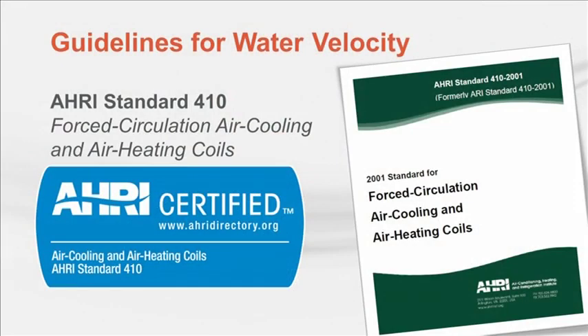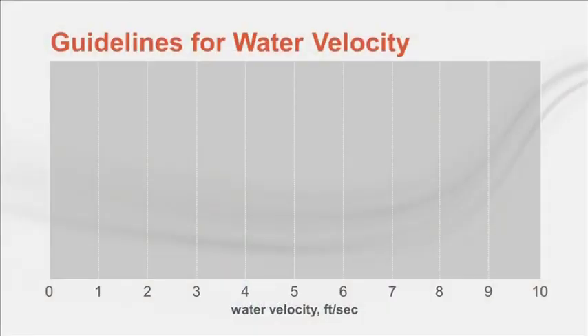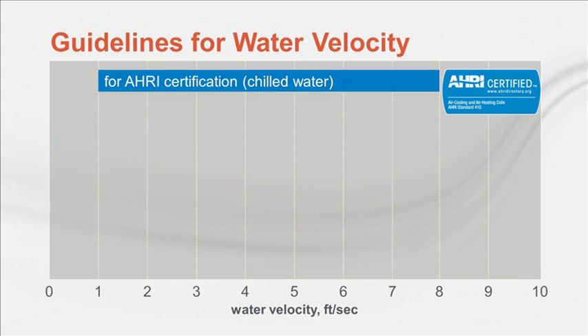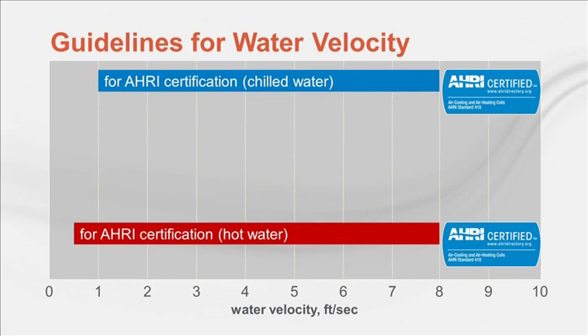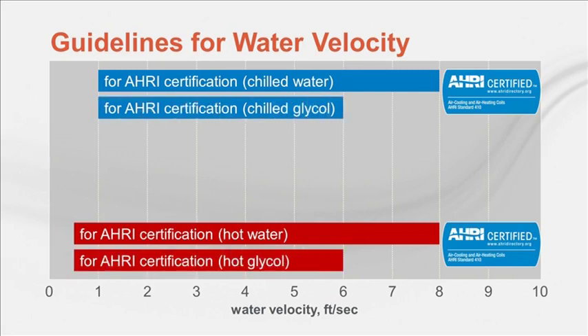Design guidelines for water velocity should take into account all of these risks. One source of guidance is AHRI, the trade association representing global manufacturers of air conditioning, heating, and refrigeration equipment. Most coil manufacturers rate and certify their performance using AHRI standard 410, which establishes testing and rating requirements for capacity, air pressure drop, and water pressure drop. For cooling coils, AHRI requires water velocity between 1 and 8 feet per second. For heating coils, 0.5 to 8 feet per second. The maximum is lowered to 6 feet per second for cooling coils using ethylene or propylene glycol.